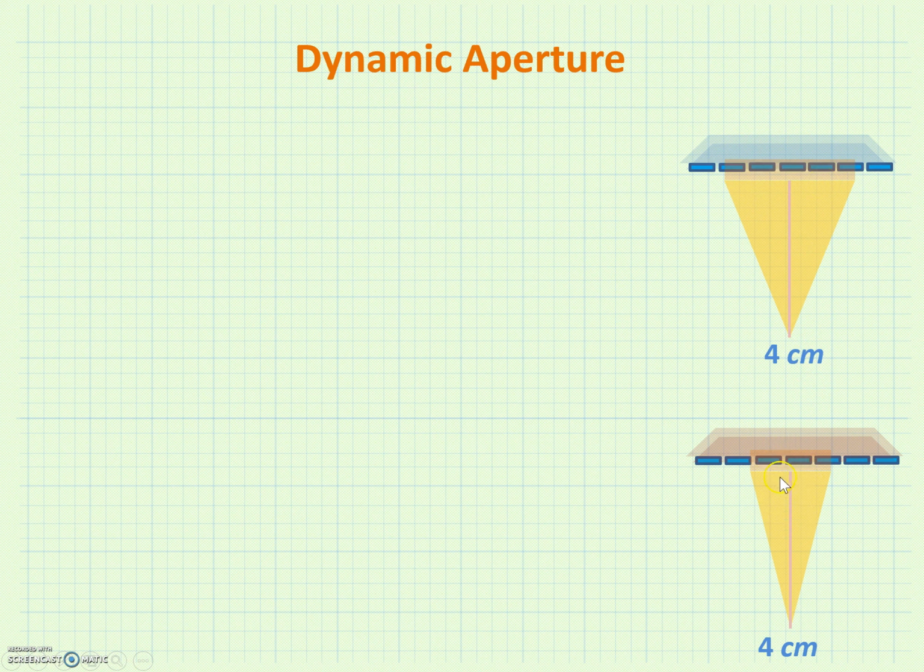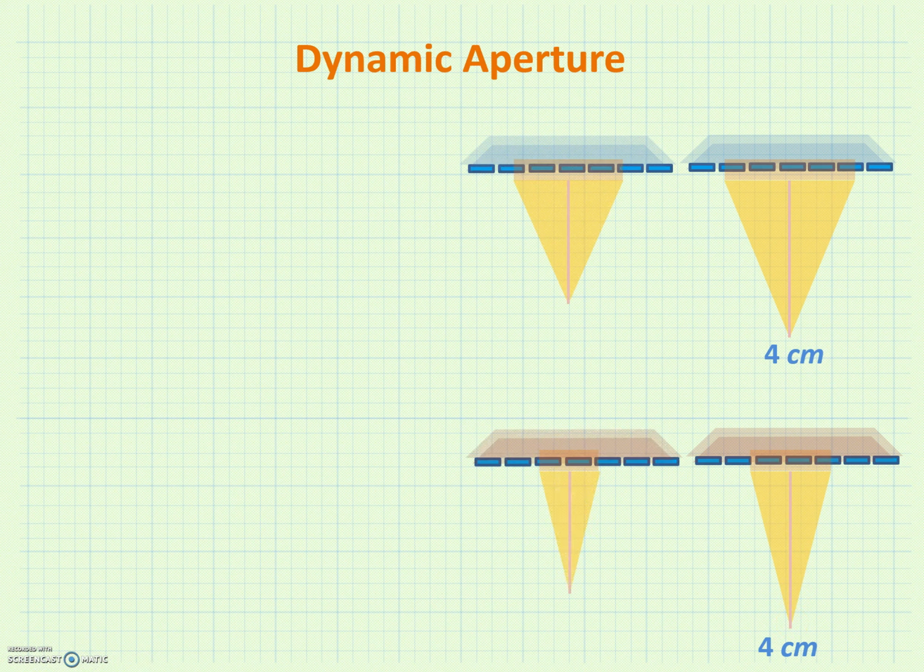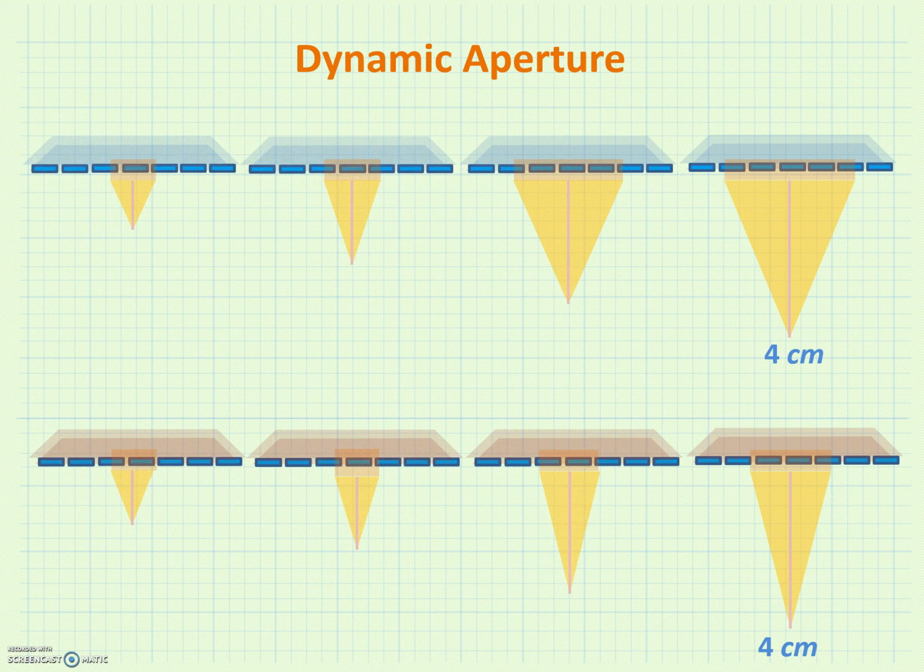But this manufacturer has a completely different aperture for the same insonation depth. And this was a study done, I think, 10 or 15 years ago. But at all different insonation depths, the aperture width actually changes without really any sort of standardization. So this will change your spectral broadening between different manufacturers, between two different pulsed wave systems.